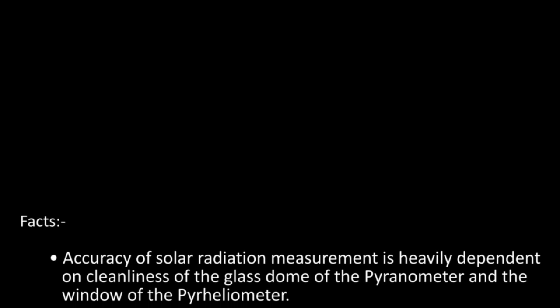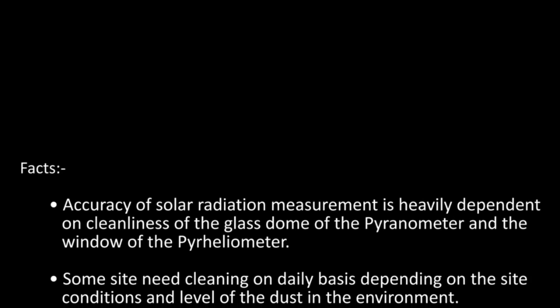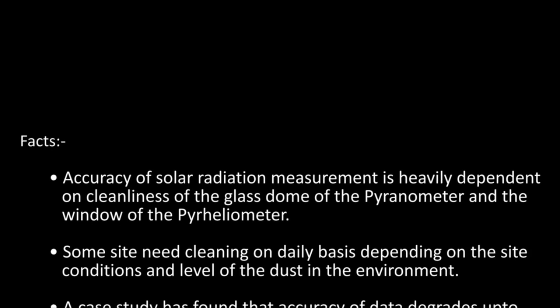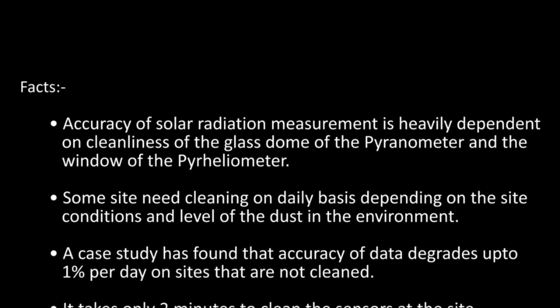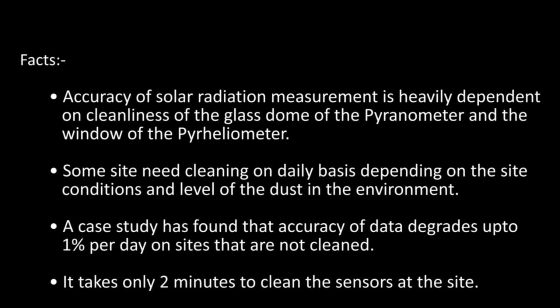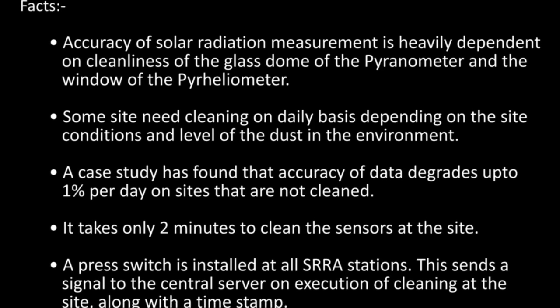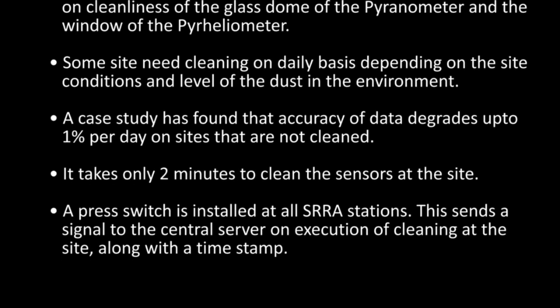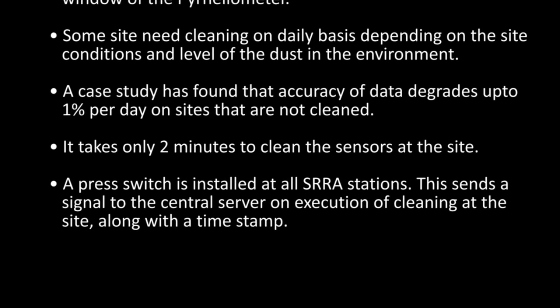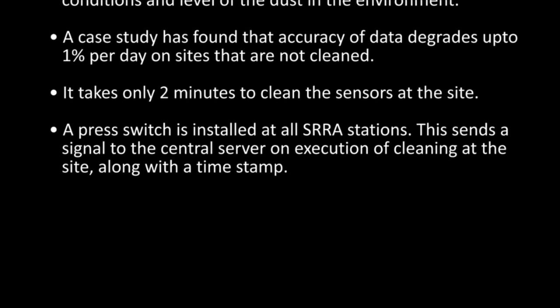Accuracy of solar radiation measurement is heavily dependent on cleanliness of the glass domes of the Pyranometer and the window of the Pyrheliometer. Some sites need cleaning on a daily basis, depending on the site conditions and level of dust in the environment. A case study has found that accuracy of data degrades up to 1% per day on sites that are not cleaned. It takes only 2 minutes to clean the sensors at the site.